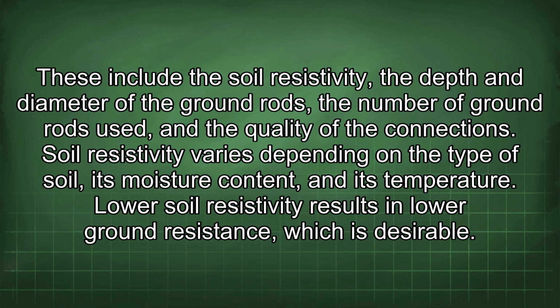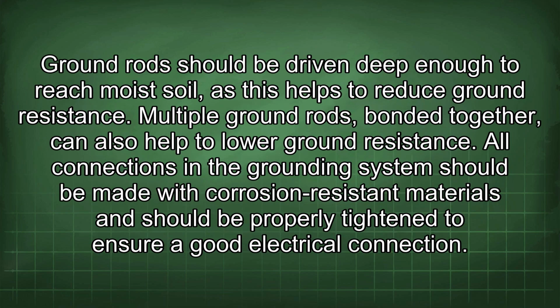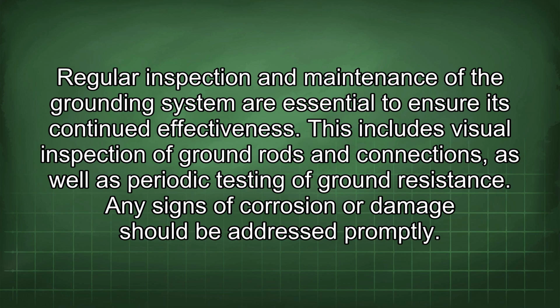Soil resistivity varies depending on the type of soil, its moisture content, and its temperature. Lower soil resistivity results in lower ground resistance, which is desirable. Ground rods should be driven deep enough to reach moist soil, as this helps to reduce ground resistance. Multiple ground rods bonded together can also help to lower ground resistance. All connections in the grounding system should be made with corrosion-resistant materials and should be properly tightened to ensure a good electrical connection. Regular inspection and maintenance of the grounding system are essential to ensure its continued effectiveness. This includes visual inspection of ground rods and connections, as well as periodic testing of ground resistance. Any signs of corrosion or damage should be addressed promptly.